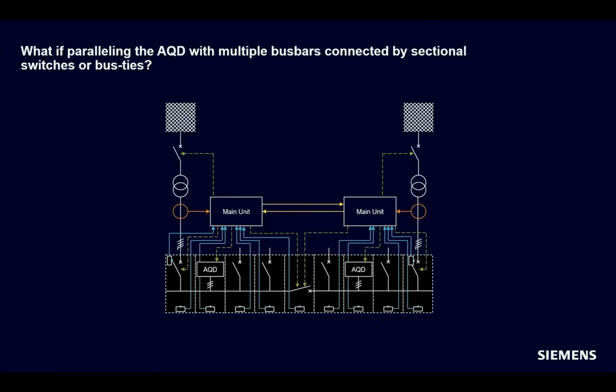Next question. What about paralleling the AQD with multiple bus bars connected by sectional switches or bus ties? Specific arcing schemes are available to consider such designs. Each section needs to be equipped with its own AQD. Depending on the state of the bus ties and incomers, the required AQD and breakers will be tripped.